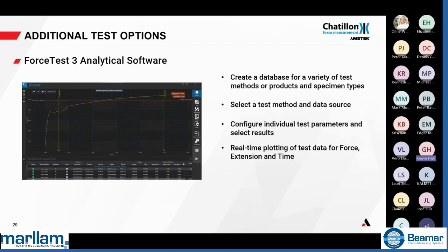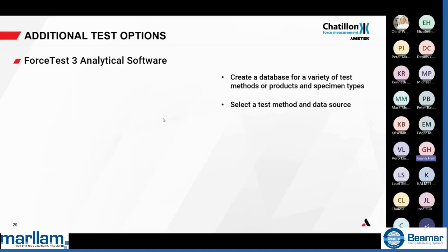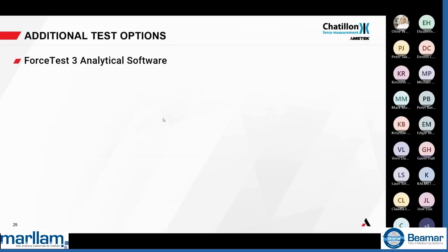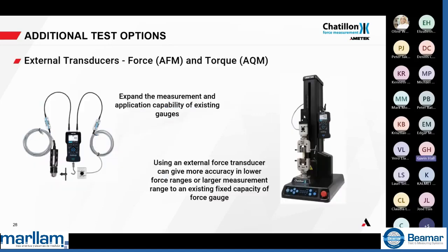And Dennis asks, how does the TCM measure extension? Well, the TCM, when it's connected to the force gauge, let's see if we've got a picture of that. When it's mounted to the main frame, you can see probably on that graphic, it's very small, but there is a force measurement, and below that there is an extension measurement. So there is an encoder in the test frame.